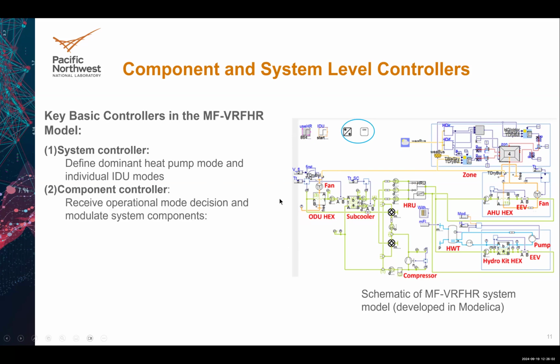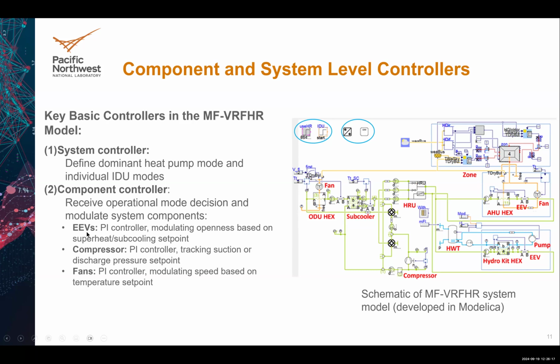Then the other is the component controller. For example, this component controller will receive the operation mode decision from the main controller, then modulate the system components such as EEVs, compressor, and fans. So the EEV, this valve, is controlled by a PI controller, modulating the opening based on either a superheat or subcooling set point. For a VRF system, we have a lot of EEVs, like AHU EEVs, hydro kit EEVs, and also ODU EEVs. So this is a very complicated system, and that's why you need a lot of EEVs.